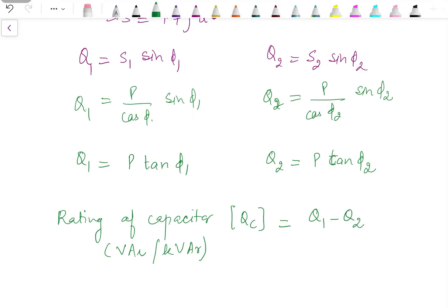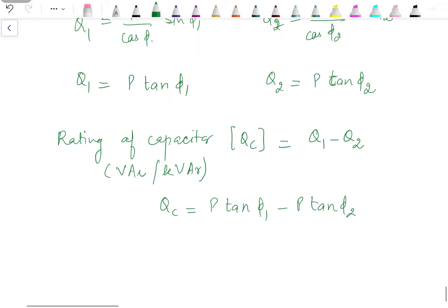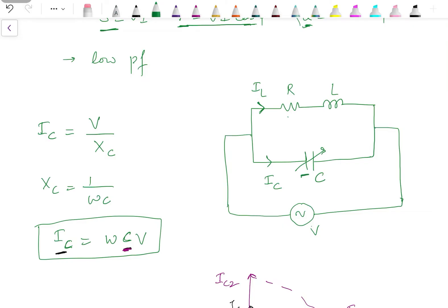Earlier the reactive power requirement was higher; now it is reduced to Q_2. Since Q_1 = P tan φ_1 and Q_2 = P tan φ_2, the rating of the capacitor is Q_C = P(tan φ_1 − tan φ_2). The purpose of the capacitor added in parallel with the load is to compensate reactive power locally, instead of withdrawing it from the supply.